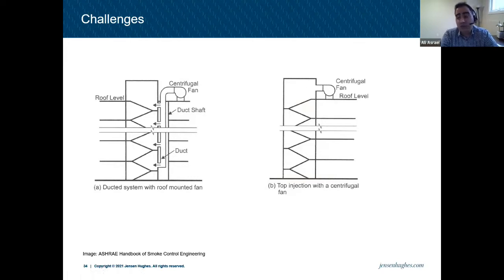And I've been in projects where I couldn't open the door. Literally, you can't just push it, and I'm relatively young. So think about other occupants in the building who want to exit, and at that point you're thinking, what's the point of this fan here, right? The exit is an exit. The first thing is you want occupants to exit the building. It's like you're locking your exit doors by overpressurizing it, right? So this is a significant issue. We've been in buildings where we worked with the fire department, and we had to temporarily decommission the fan because we wanted the exit to be an exit first, and then think about pressurizing it.